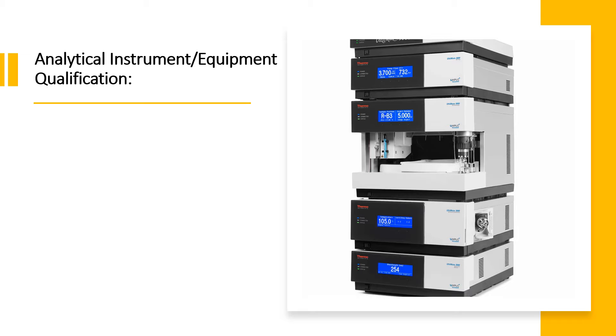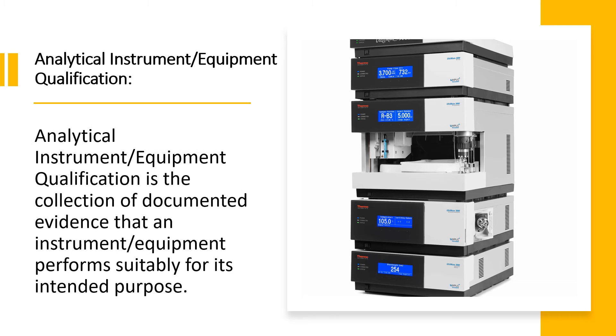Now first, we will discuss what is analytical instrument or equipment qualification. The basic definition is: analytical instrument equipment qualification is the collection of documented evidence that an instrument or equipment performs suitably for its intended purpose. The analytical instrument will be used to analyze various pharmaceutical samples — it may include raw material, in-process samples, finished products, and stability samples. Results obtained from these instruments shall be used to release materials and products, and based on these results, the quality of the product or materials shall be ensured. Hence, it is very important to qualify the analytical instrument to ensure that the instrument performance is satisfactory and the instrument will not give any faulty results.